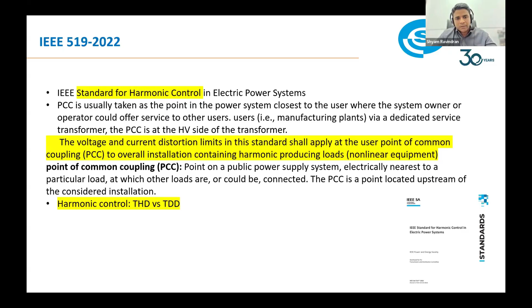So PCC is the only point of measurement we want to look at power quality issues from the regulatory perspective. Harmonic control is no more THD, it has moved to TDD as explained in the previous slides. This standard shall be applied at interface points between system operators or owners, usually the distribution licensee, and the users in the power system.